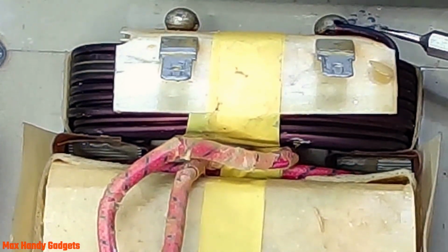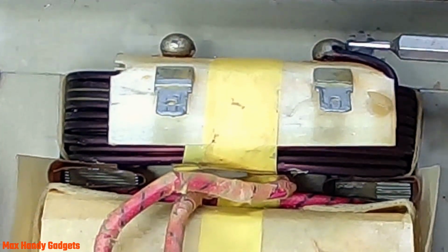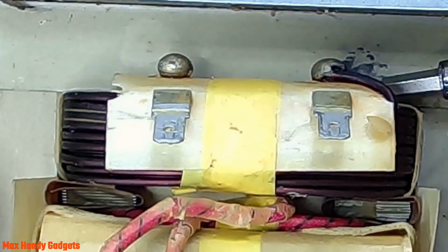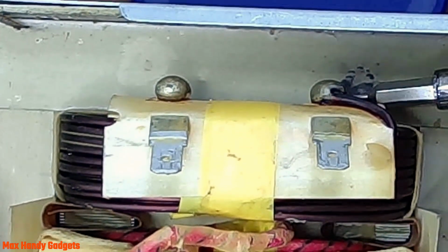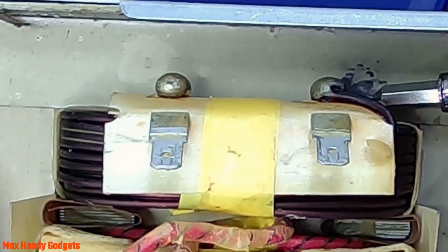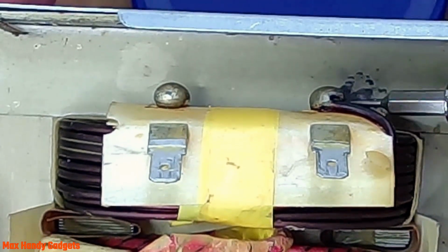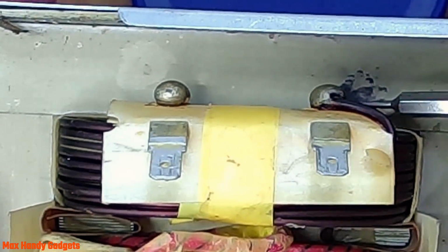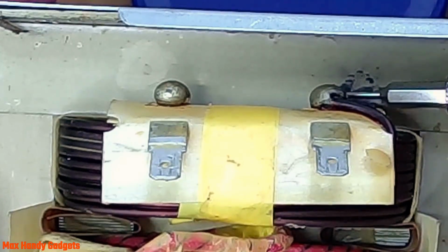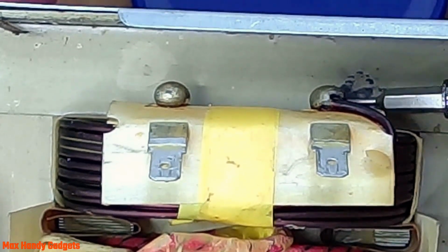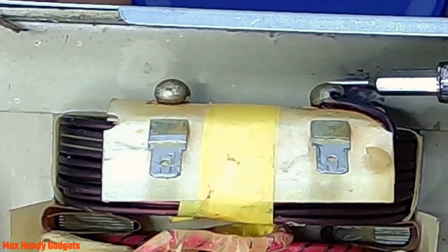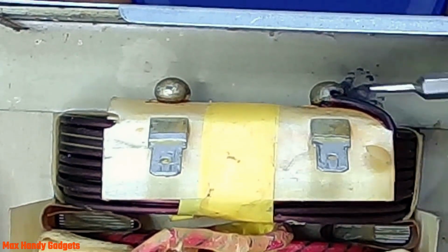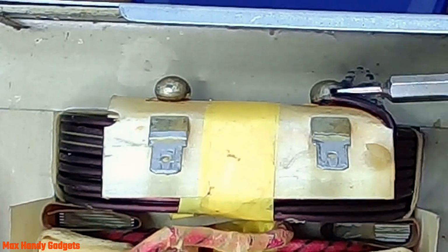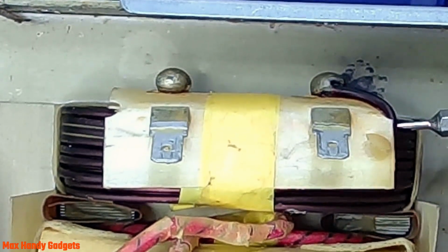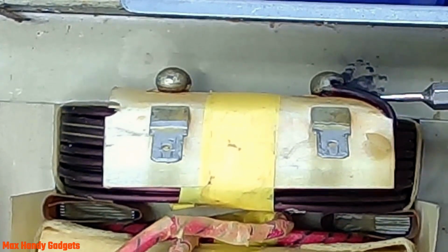Yeah, there it is, right there. Can you see it? That winding is going through that solder joint, and it's bound up at the bottom there between a piece of plastic and the ground. You can see where it was arcing, it was definitely arcing. So maybe that's why it's shorted to ground. Now that's the end of this terminal here, so I don't think it damaged the rest of the windings. It just seems like this part right here arced to ground.